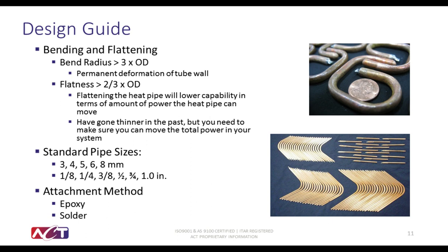A heat pipe can also be flattened. ACT recommends flattening a heat pipe no more than 2/3 of its OD, i.e., for a 6 millimeter heat pipe, you'd like to flatten that to no less than 4 millimeters. ACT uses standard pipe sizes to generate heat pipes, meaning that any pipe size from a 3 millimeter to a 1-inch diameter can be used to create a functioning heat pipe. That heat pipe is traditionally attached to either your evaporator or your condenser via epoxies or solders.